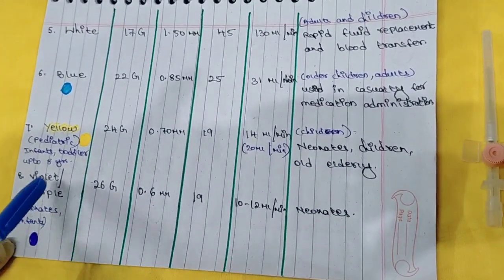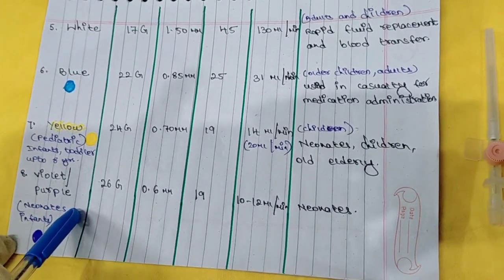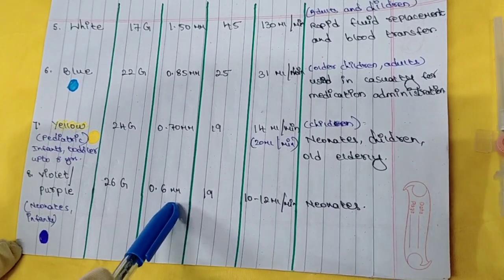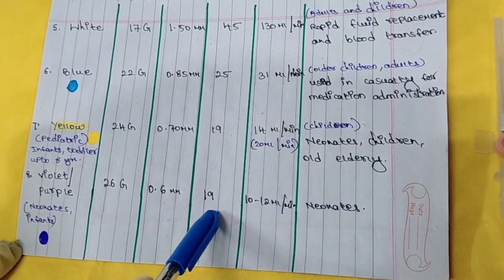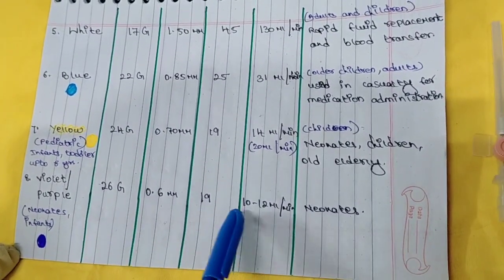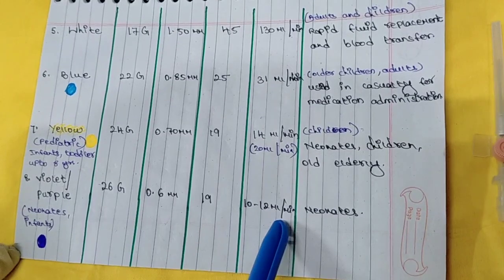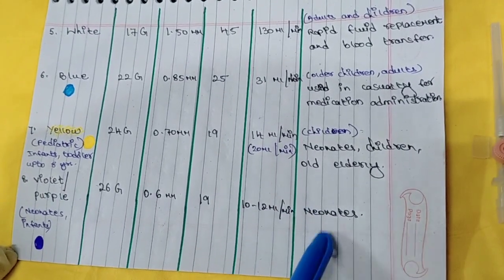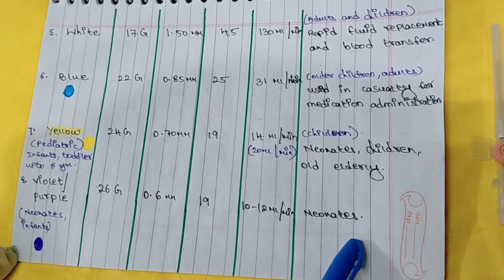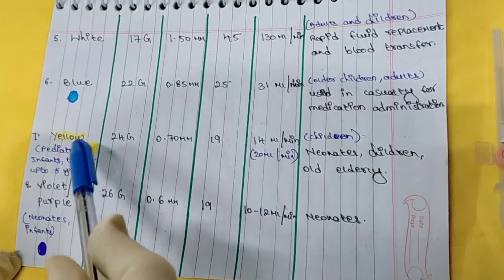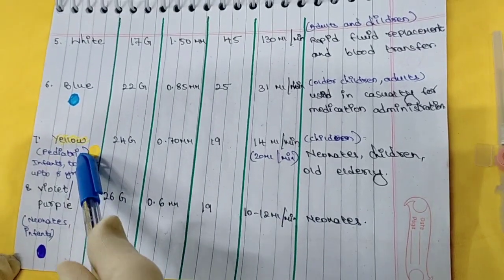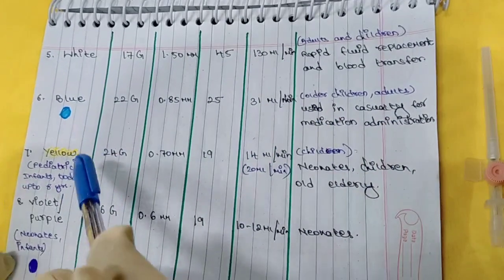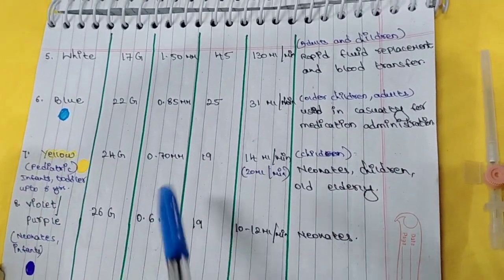Then the last one is the violet or purple cannula, which is 26 gauge. The outer diameter is 0.6 mm and the catheter length is 19 mm. The flow rate is 10 to 12 ml per minute, and this is used mostly in neonates and infants. So we can say that yellow and violet or purple cannulas are pediatric cannulas, mostly used in pediatrics.